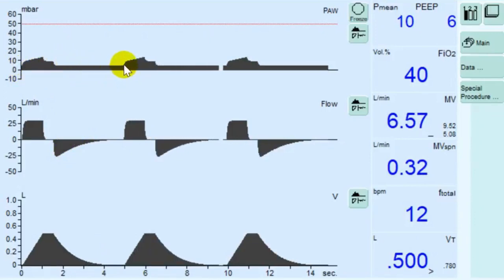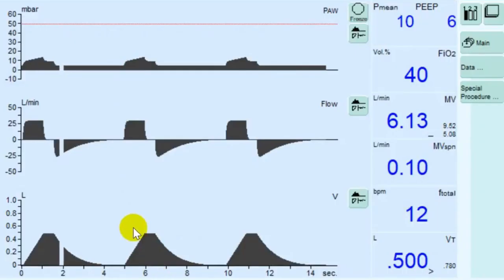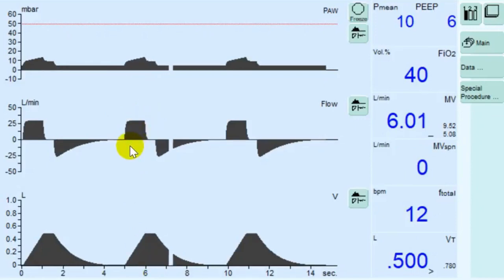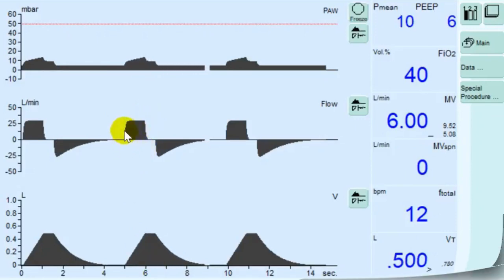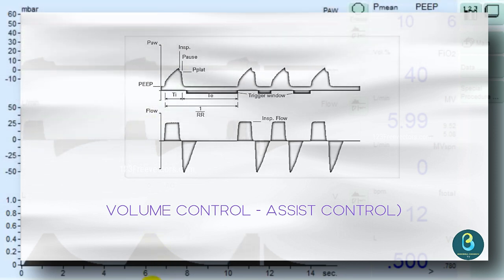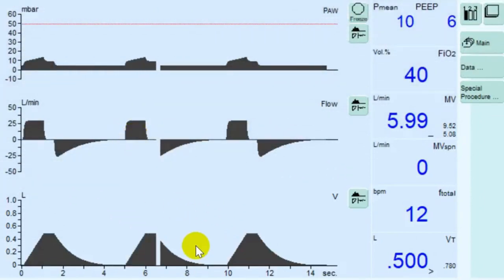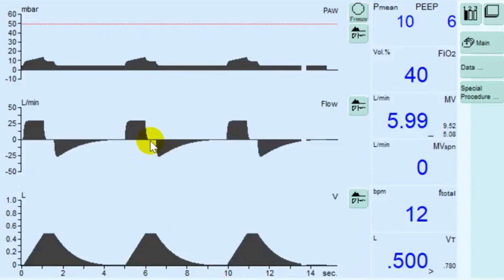The next mode of Volume Control Ventilation is Volume Control Assist Control. The patient always receives at least the set tidal volume. Every detected inspiration effort of the patient at PEEP level triggers an additional mandatory breath, so the patient determines the number of additional mandatory breaths. To give the patient sufficient time for expiration, it is not possible to trigger another mandatory breath immediately after a completed breath.